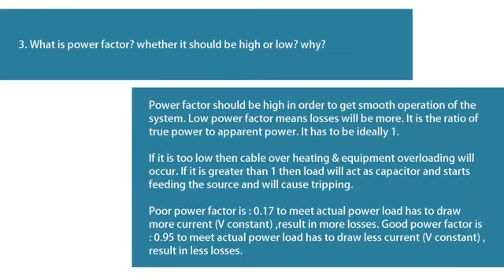Question 3: What is power factor? Whether it should be high or low? Power factor should be high in order to get smooth operation of the system. Low power factor means losses will be more. It is the ratio of true power to apparent power, and it has to be ideally 1. If it is too low, cable overheating and equipment overloading will occur. If it is greater than 1, then the load will act as a capacitor and starts feeding the source, causing tripping. Poor power factor of 0.17 means the load has to draw more current, resulting in more losses. Good power factor of 0.95 means the load has to draw less current, resulting in less losses.